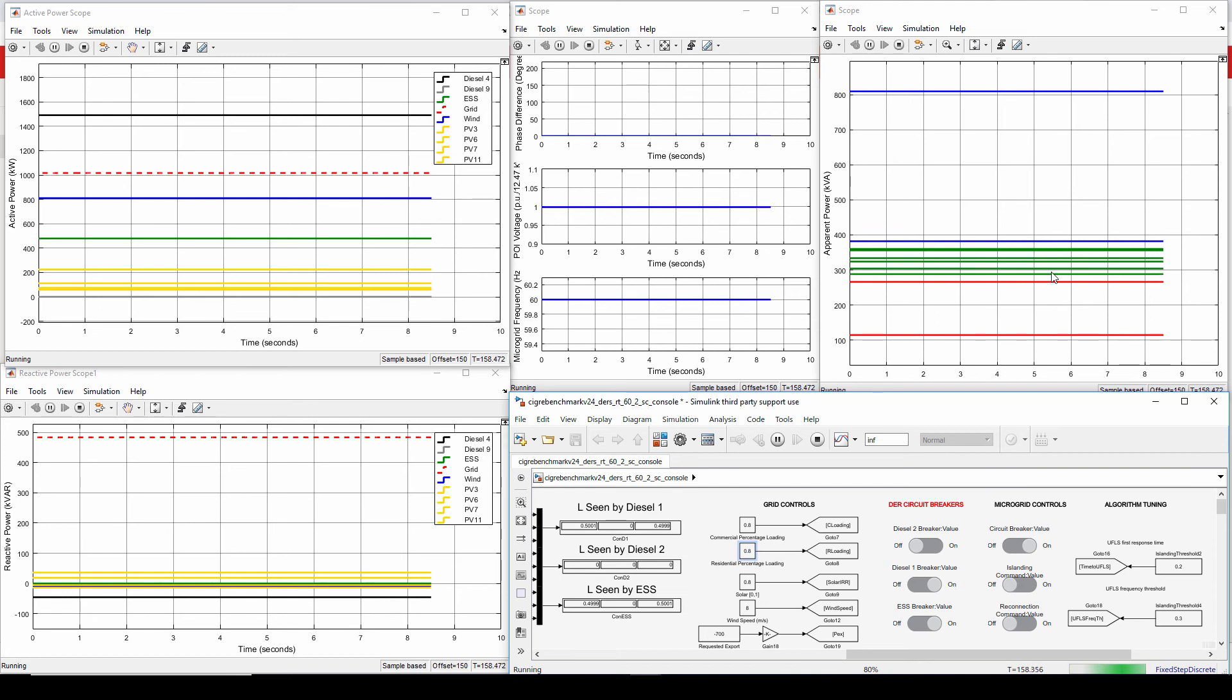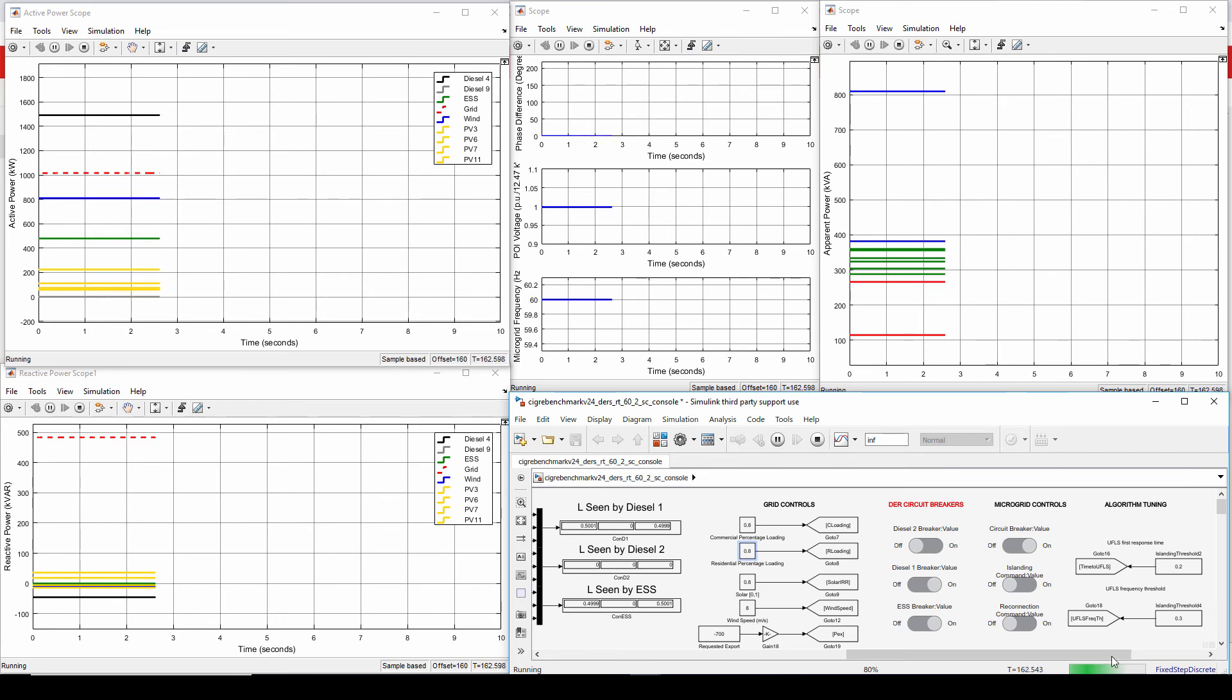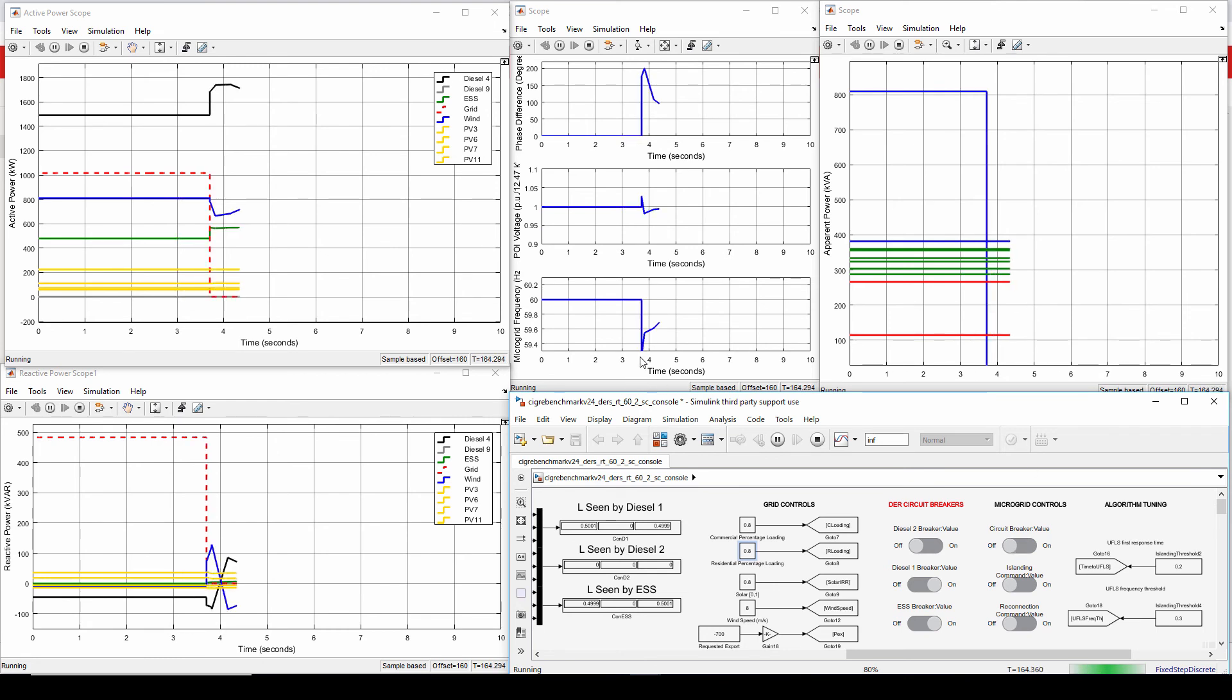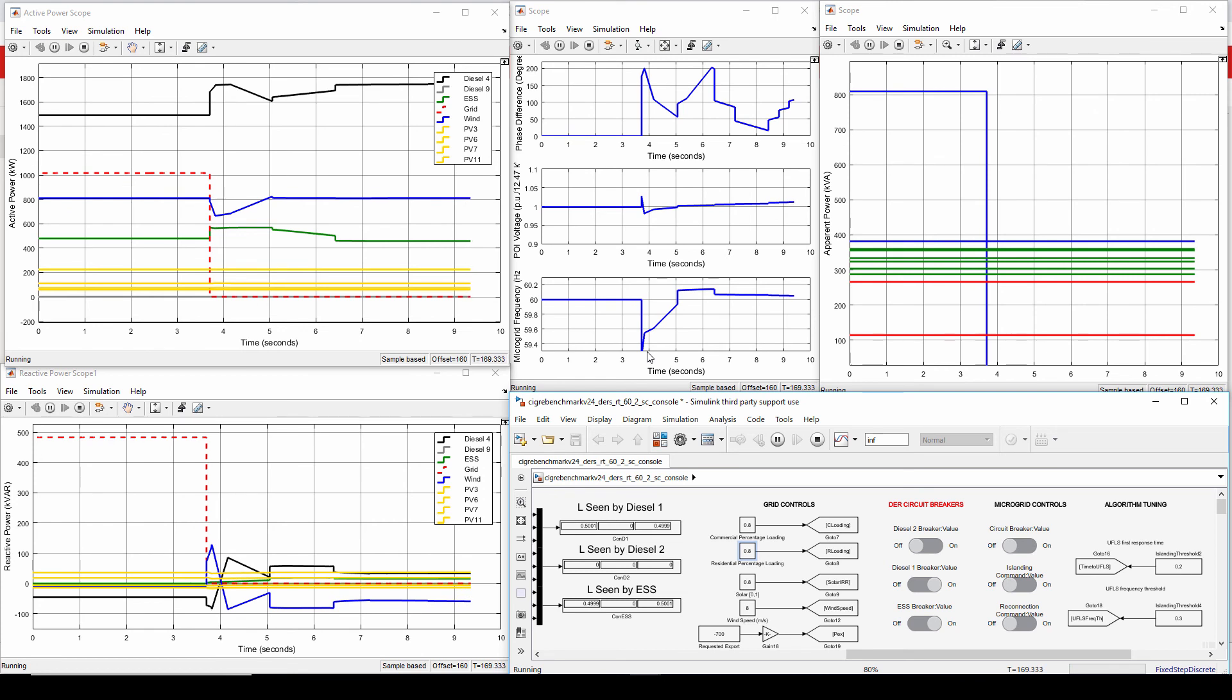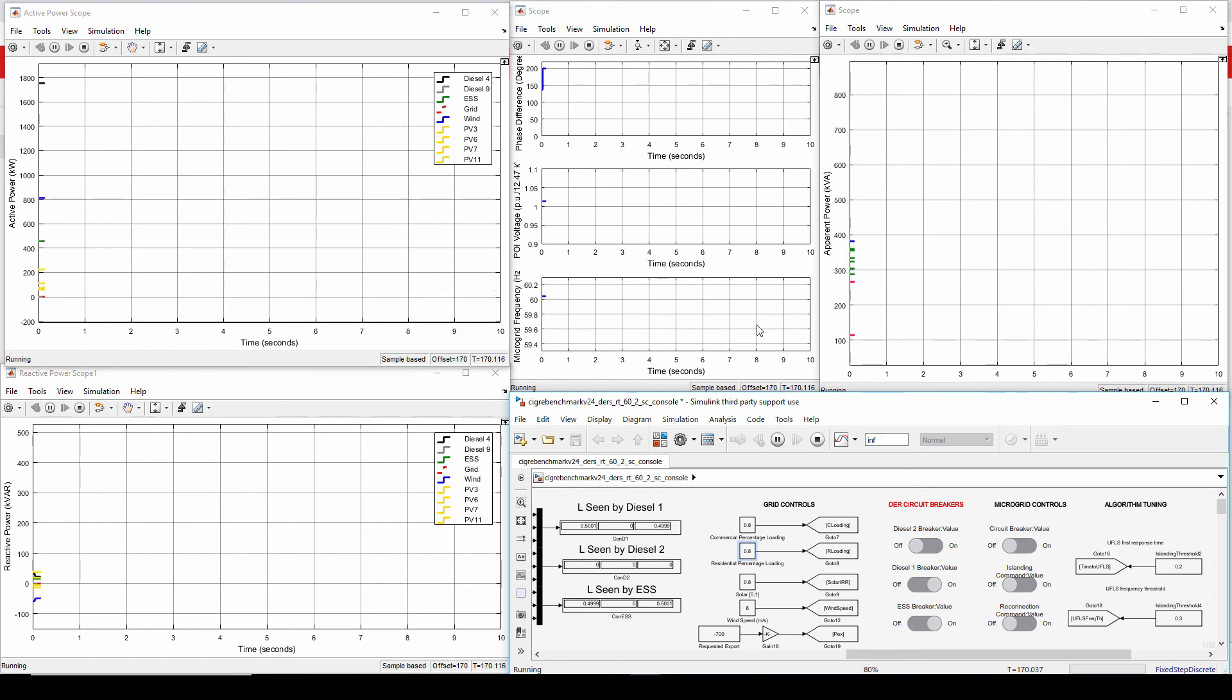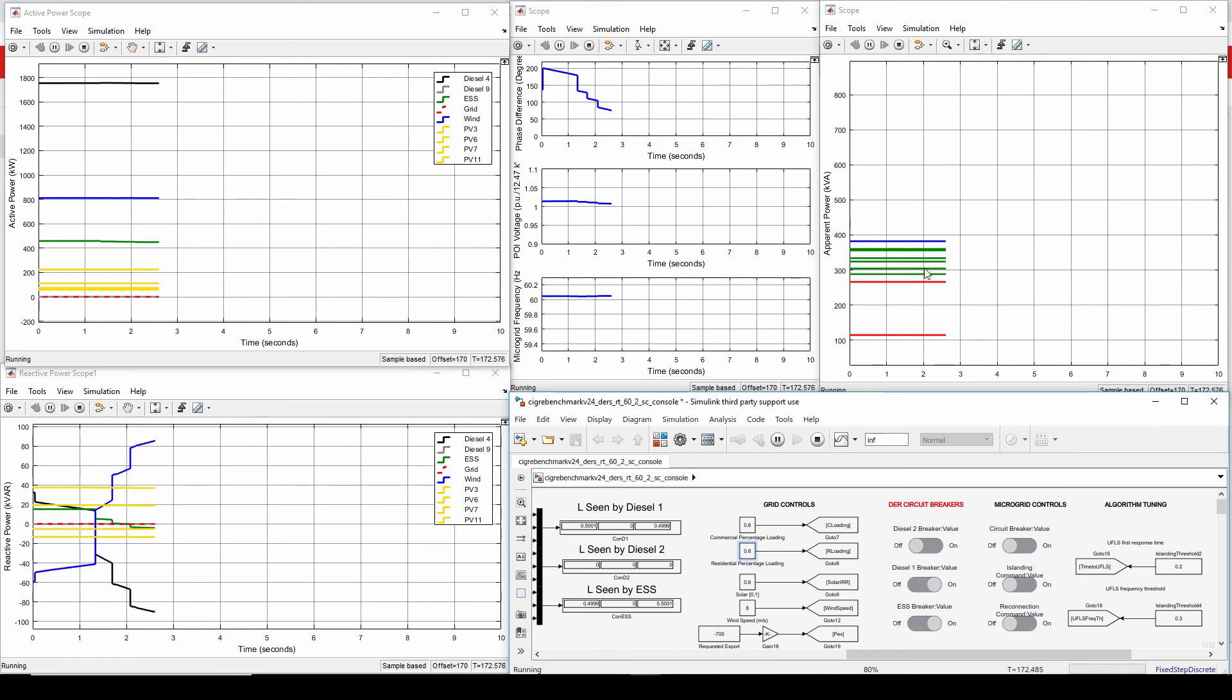And what it does basically is that it lets the load agents agree on who is the least critical and the largest to shed first. And here is the algorithm tuning for this. So now I'm going to simulate that. As you can see here, unplanned islanding has been issued now and there was a very sharp frequency drop, but then the algorithm was able to save the system from microgrid instability by shedding the largest non-critical load. If that frequency deviation would maintain, then the next largest non-critical load would be shed. And so that is unplanned islanding with under frequency load shedding.